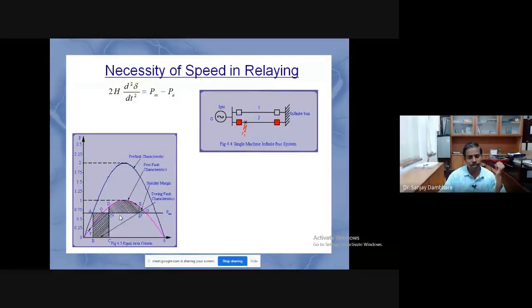We study this case from the transient stability perspective with that famous equal area criterion, and you will appreciate that the limiting case will be area A1 equals area A2. Now the point is that these areas A1 and A2 depend upon when the faulty part is being removed. The removal of the transmission line, the operation of the circuit breaker of this transmission line, will decide where this point C is. And you can understand that if the protection system operation is fast, then this area can be reduced, and you have a safer margin to keep your power system in a transiently stable mode.